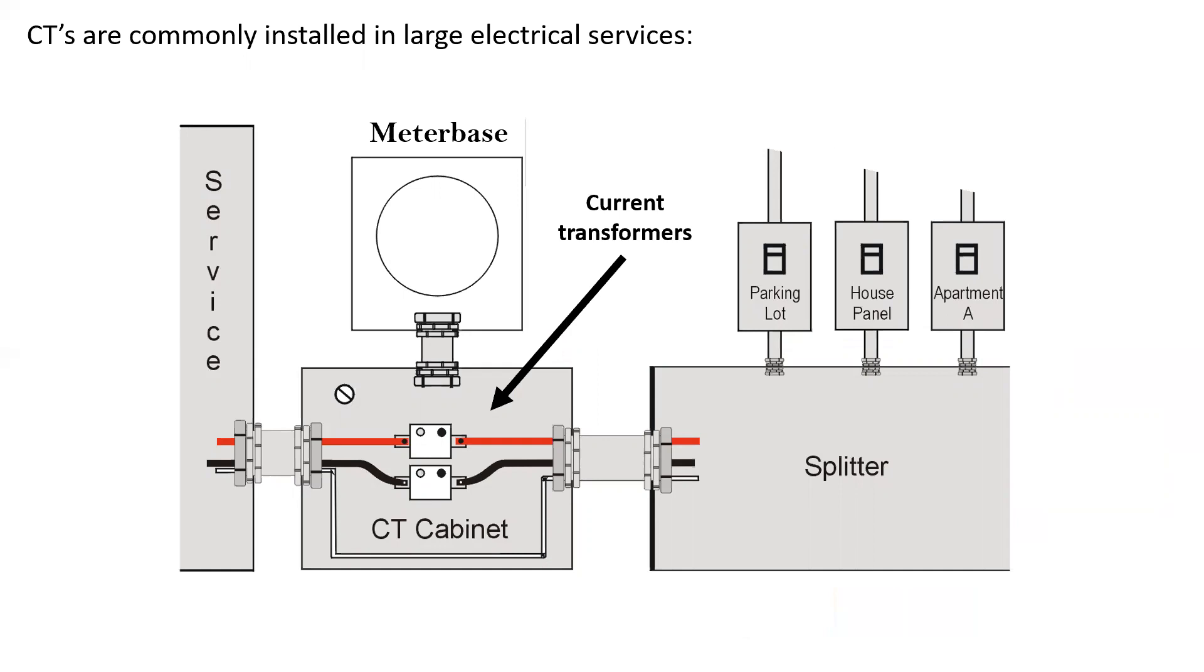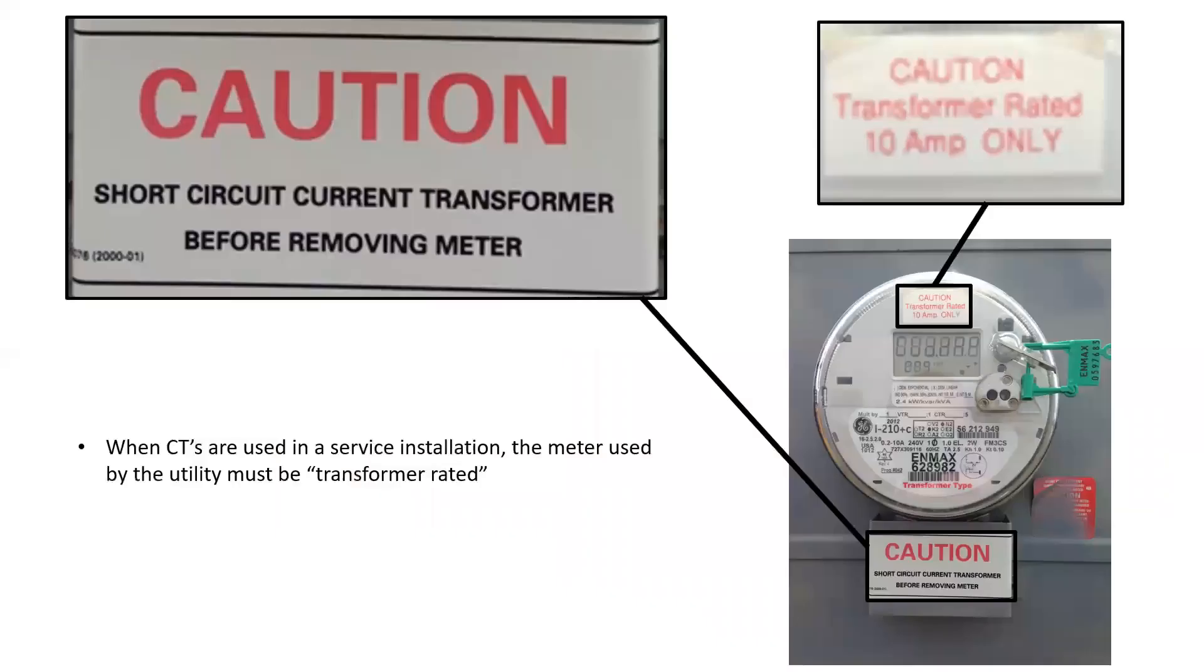So, where do we commonly see these installed? Well, a lot of electrical services will have CTs because the amperage value far exceeds the rating of a standard line value rated meter. So, we have a CT cabinet with CTs inside the cabinet, and then we have conductors that come off of the secondaries and go up into the meter base and connect to the meter itself. Of course, we have to use a different meter. So, this is an example of a transformer rated meter. It says transformer rated 10 amps only, which is much different than the standard meter that you would have in your house that's probably rated to 200 amps. Also connected, states here, short-circuit current transformer before removing meter. So, they don't want someone just pulling the meter off without first short-circuiting the CTs in the CT cabinet.